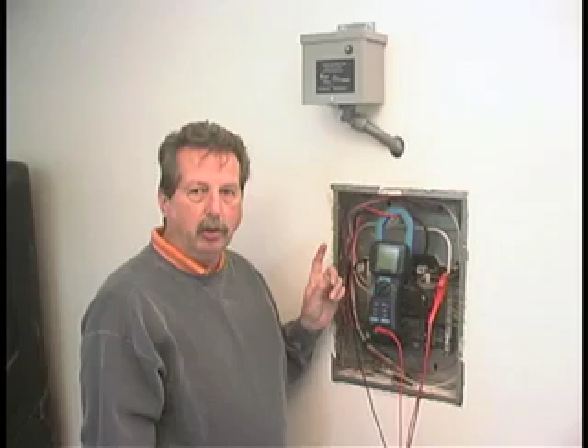Here we have a typical installation of a PU 1200. All of our units are surface mount. In this particular case, there's been a hole drilled with the wires coming in the top. There are 3 wires. 2 of them go to a dedicated 2-pole 20-amp breaker. 1 goes to the ground bar.